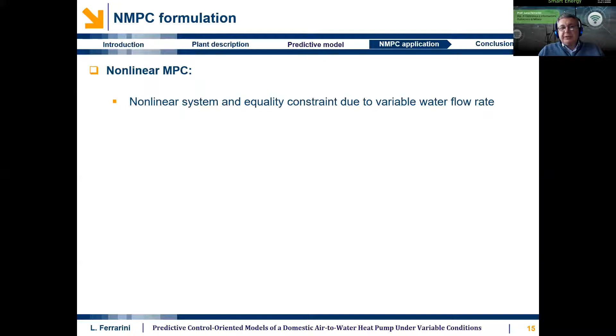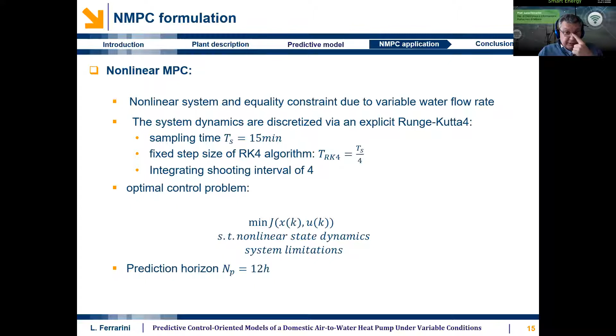And then we used some, let me say, classic technique to discretize the system through a classic Runge-Kutta algorithm with integrating shooting interval of 4. And then we solved a discrete optimization problem with a prediction horizon from 6 to 12 hours. Nothing changes. We compared what we did with this optimal control problem with the classic heating curve control, which basically it's a table, it's a function, which tells you which is the right temperature for the tank based on the external temperature, more or less.